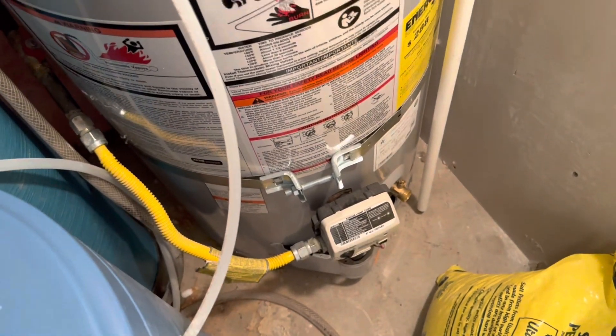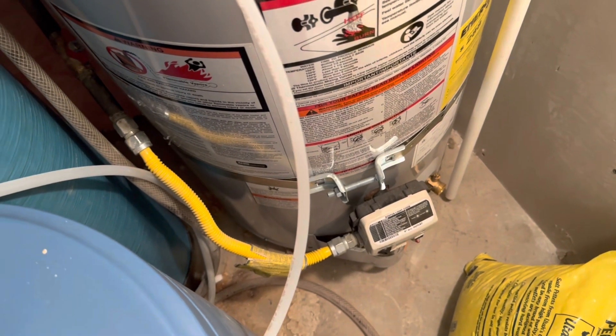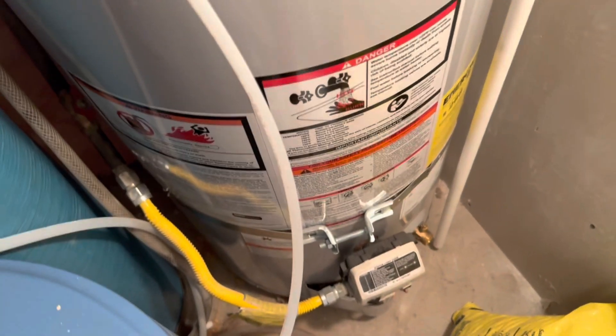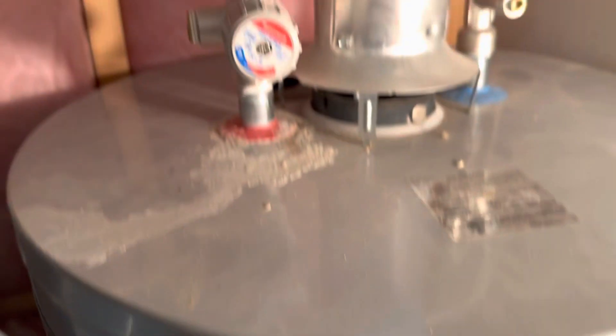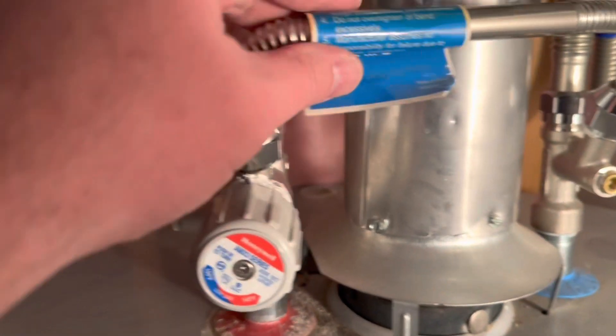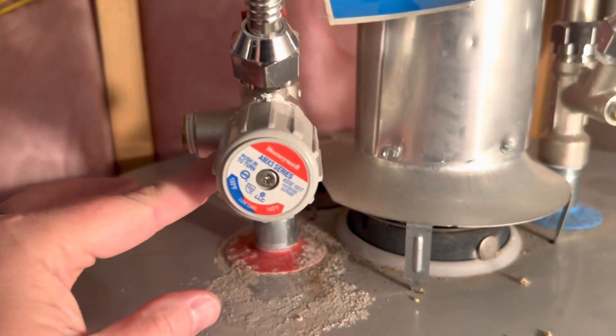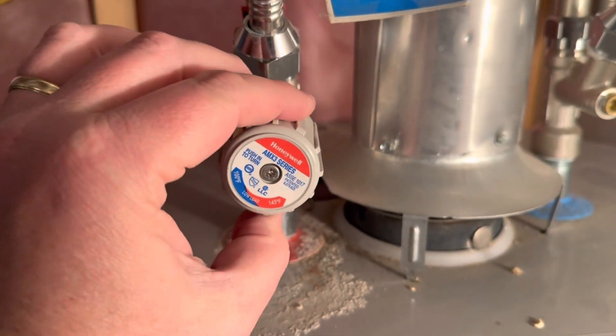But with this in place, you can crank up the water heater, giving you a lot more heat basically. It takes less hot water to mix in with cold — mixes in the mixing valve — and then sends that water at a reduced temperature out to the house.